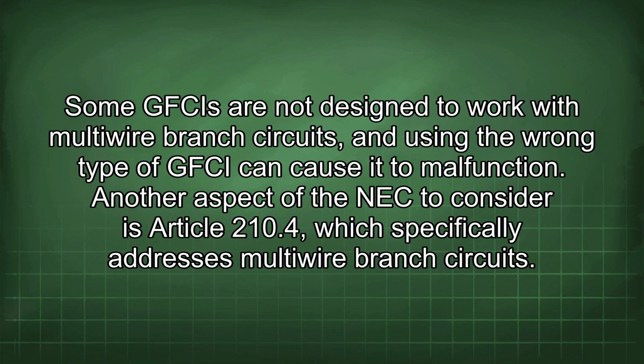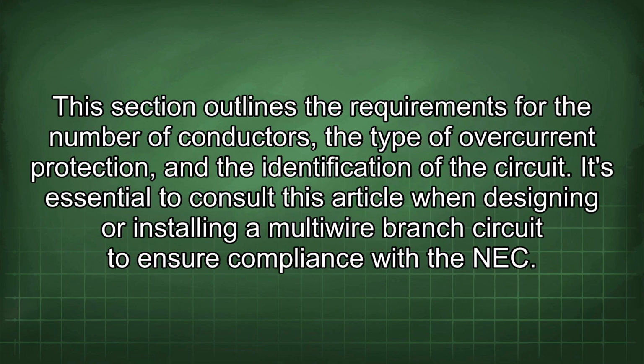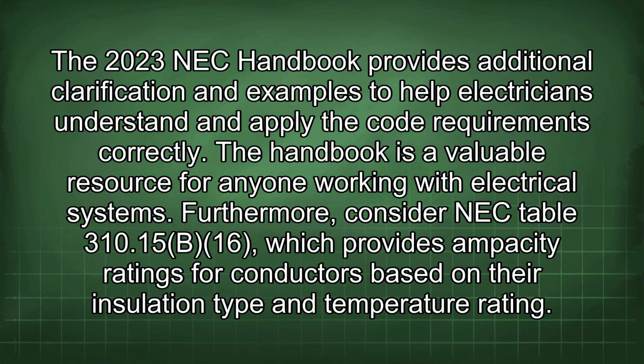Another aspect of the NEC to consider is Article 210.4, which specifically addresses multi-wire branch circuits. This section outlines the requirements for the number of conductors, the type of overcurrent protection, and the identification of the circuit. It's essential to consult this article when designing or installing a multi-wire branch circuit to ensure compliance with the NEC. The 2023 NEC Handbook provides additional clarification and examples to help electricians understand and apply the code requirements correctly. The handbook is a valuable resource for anyone working with electrical systems.